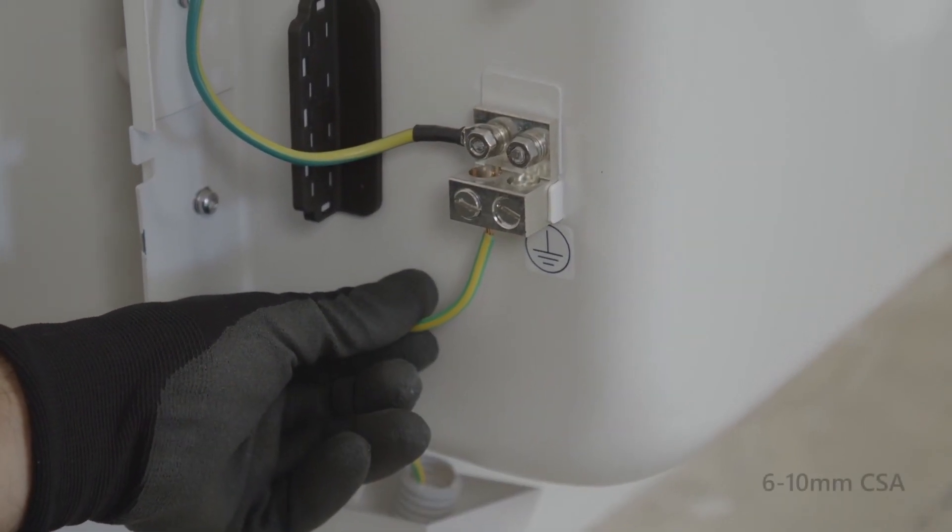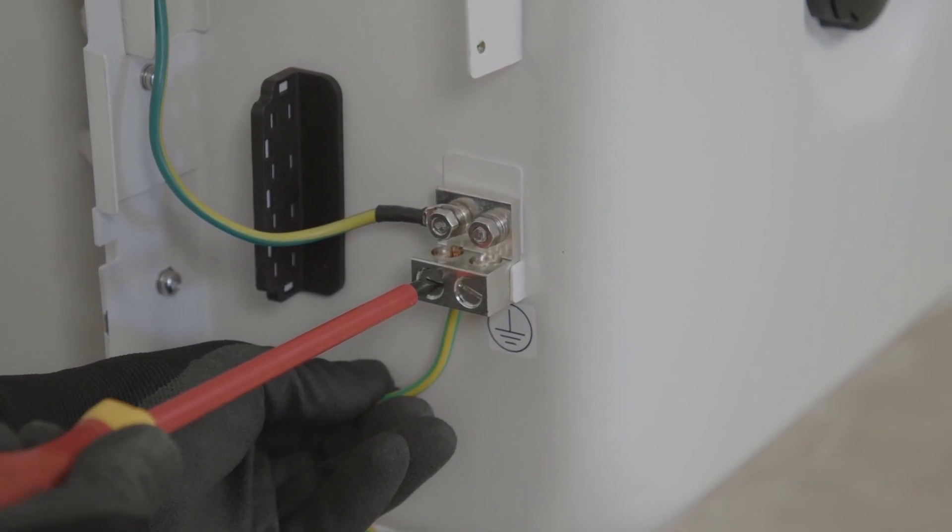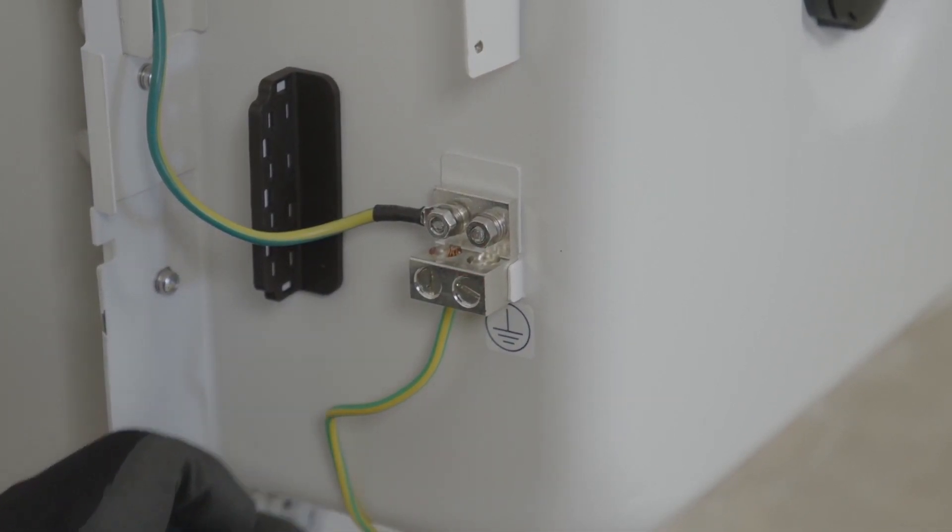Simply wire the earth to the earth terminal bar using either 6 to 10mm CSA cable. You'll notice that the earth terminal has two fixings, that's for if two batteries are being paralleled together.